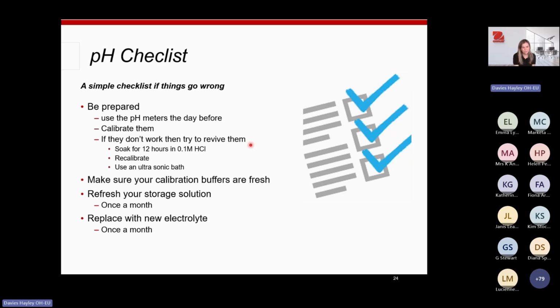So use the pH meters the day before, make sure that they've been calibrated, and if needed, condition them, clean them, recalibrate them. Bit of a checklist here. If they don't work, you can revive them in your 0.1 molar HCl for 12 hours. Again, recalibrate. If you've got any that are particularly dirty, you can put that solution into a beaker, into the ultrasonic bath, to really agitate any dirt and grime away from the electrodes.